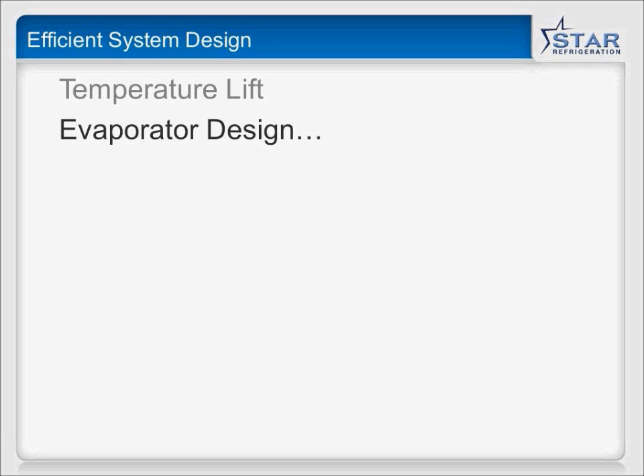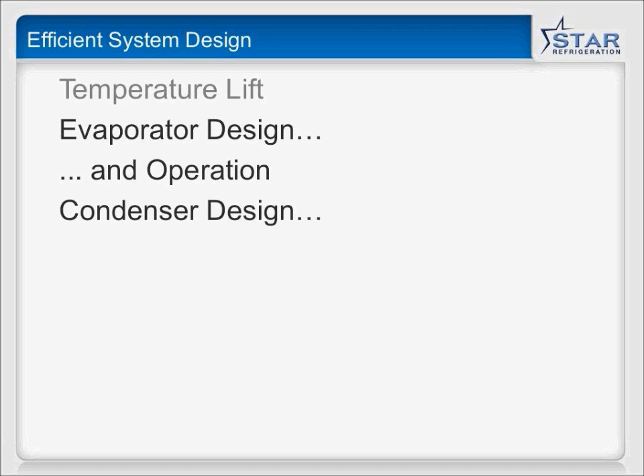The operation of the evaporator, how well is it performing? Is it performing close to that theoretical design, or is it much further away? Condenser design, this is really where things start getting out of whack. It's quite hard to have an evaporator that's not performing reasonably well. It's very, very easy to have a condenser that's performing really pretty poorly.